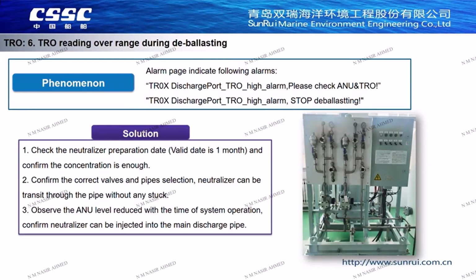TRO high alarm during deballasting. In addition to ensuring the normal expiry date of TRO reagents, please check whether the neutralizer is still valid and the concentration matches the required standard. The neutralizer is valid for 1 month after preparing.